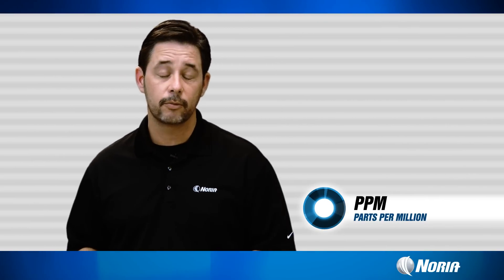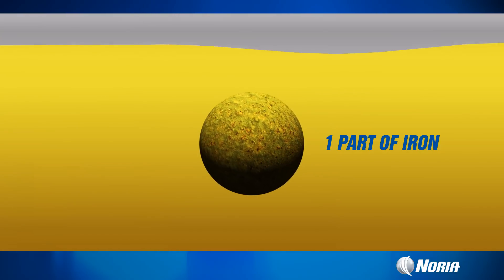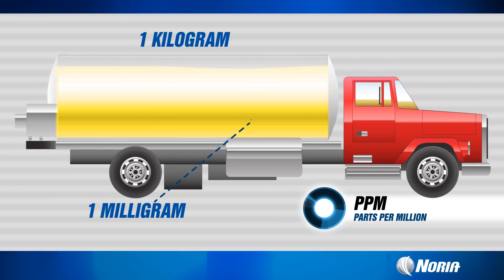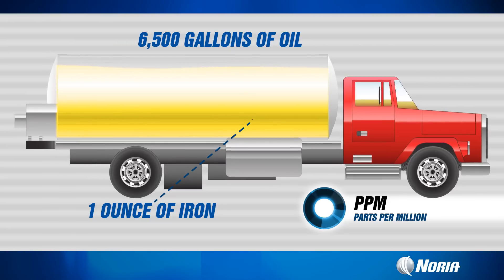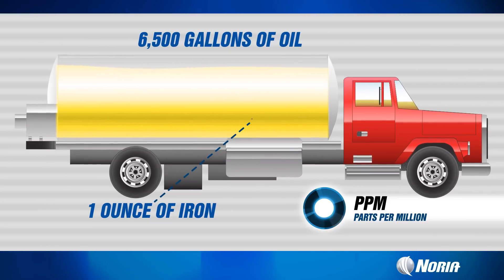What can we expect to see with elemental analysis? Well, this is where we get our parts per million values. The unit of measure is parts per million. What is a parts per million? It's basically one part of iron in a million parts of oil, or one milligram per kilogram, or one ounce of iron in 6,500 gallons of oil. That equates to one part per million.